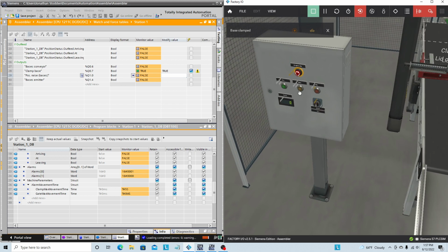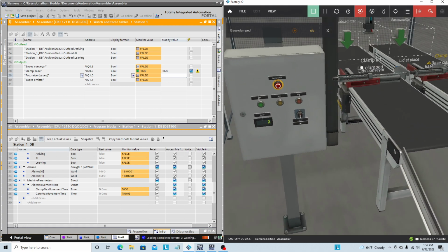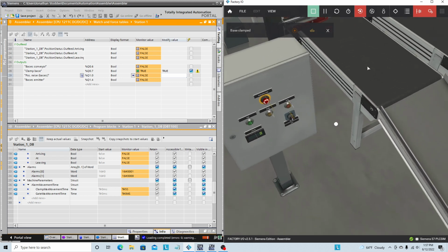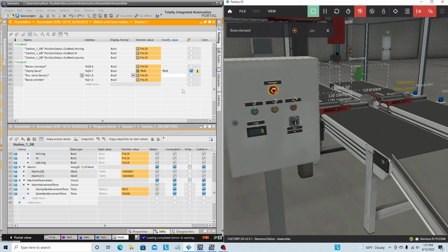Years ago, I had a machine that a technician thought was being slick, and on the backside of the reset, they wired a jumper across it, and they just kept this machine running. We had a barcode reader that was checking parts as they'd come down the line and read the barcode on them, but the barcode reader wasn't working, so they jumpered across the reset, and then all of a sudden it would pass everyone, even if the barcode was missing. And yeah, we ended up opening the panel up, and I saw that jumper in there. So that was kind of frustrating. But this way you can't get by doing that stuff. You can't just hold the reset button and spam it.